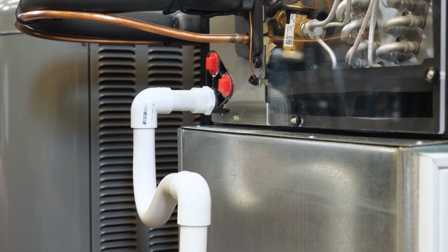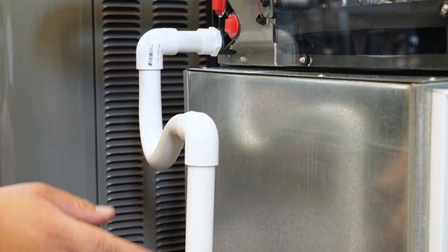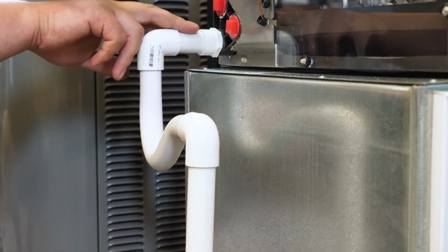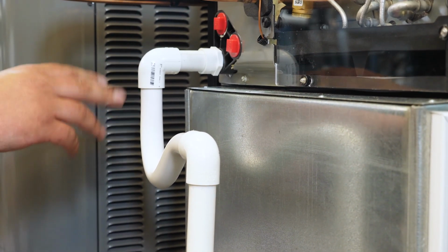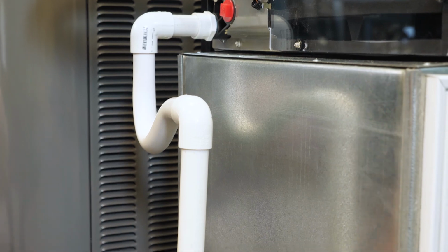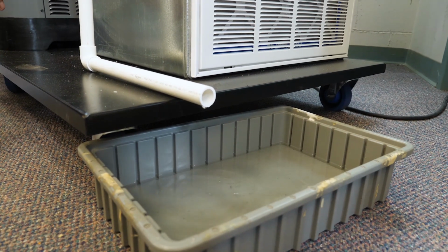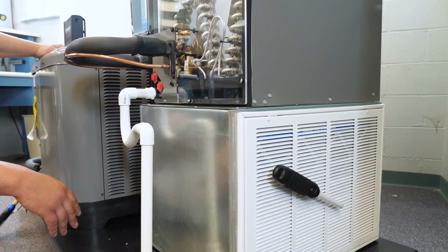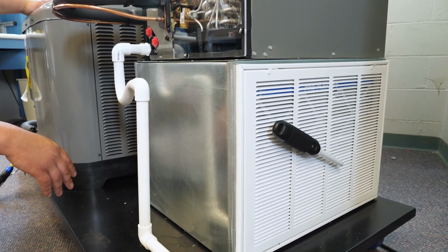So all the 3/4 PVC will be in the box that you need to install. So there will be a short piece here going down to an elbow and a P-trap. Another elbow, and then we've got 2 lengths of PVC just to get the condensate drain away from the frame, and then any sort of bucket to collect water underneath that.